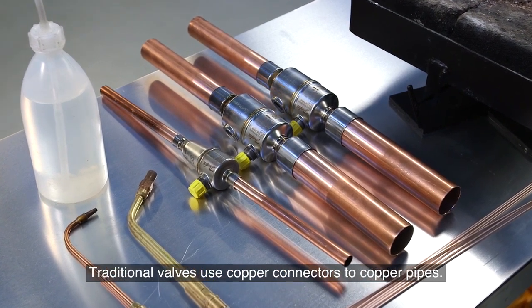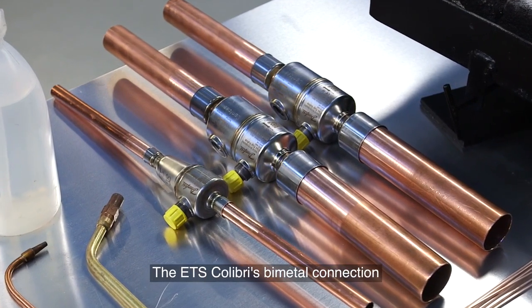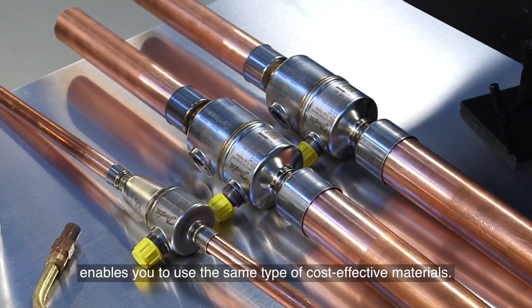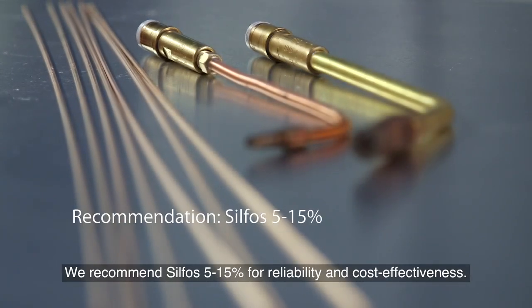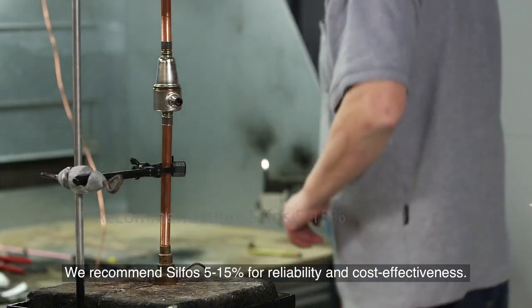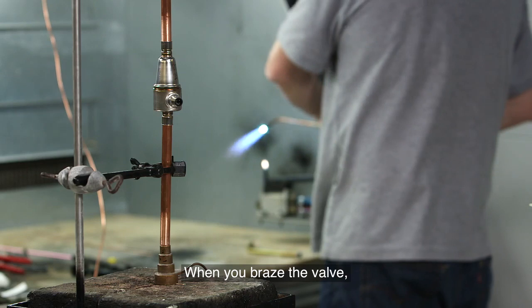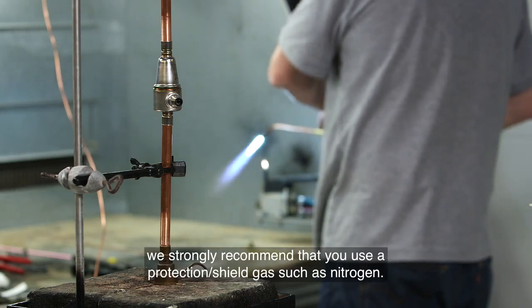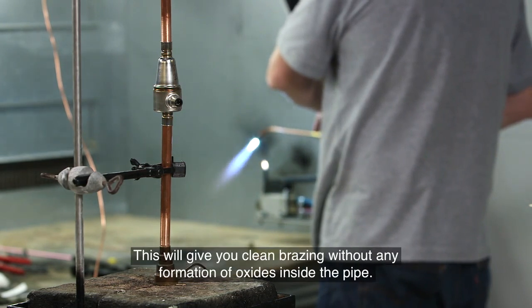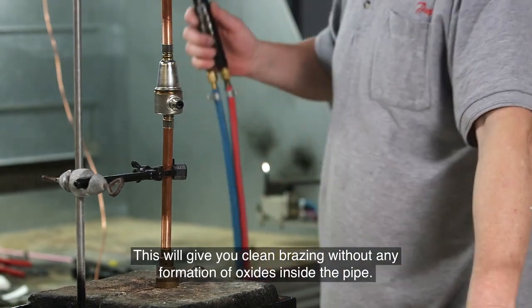Traditional valves use copper connectors to copper pipes. The ETS Colibri's bimetal connection enables you to use the same type of cost effective materials. We recommend Silfos 5-15% for reliability and cost effectiveness. When you braze the valve, we strongly recommend that you use a protection shield gas such as nitrogen. This will give you clean brazing without any formation of oxides inside the pipe.